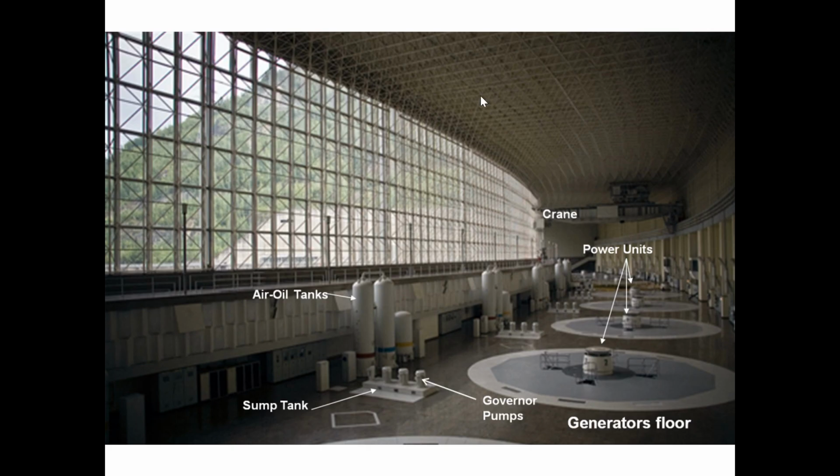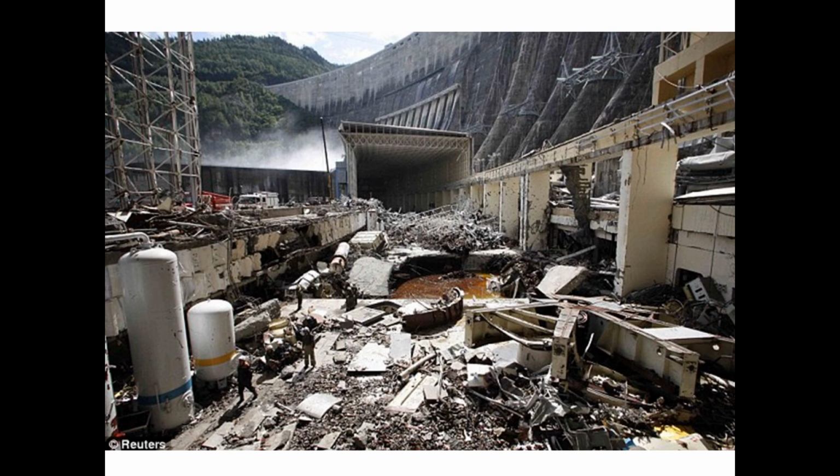And unfortunately, several of the bolts that were holding the generator in place were disconnected, and several more of the bolts had cracks and fatigue because they were decades old and they hadn't been testing to make sure that the bolts still had the strength that they ought to. And what happened was one day it just all spectacularly failed.